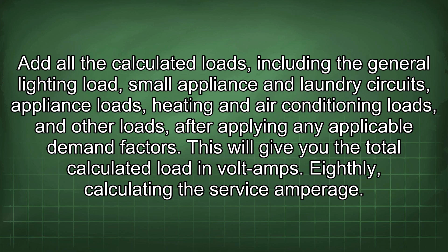Eighthly, calculating the service amperage. Divide the total calculated load in volt amps by the voltage of the service, which is typically 240 volts for a residential service. This will give you the required service amperage. For example, if the total calculated load is 30,000 volt amps, then the required service amperage is 30,000 volt amps divided by 240 volts, which equals 125 amps.